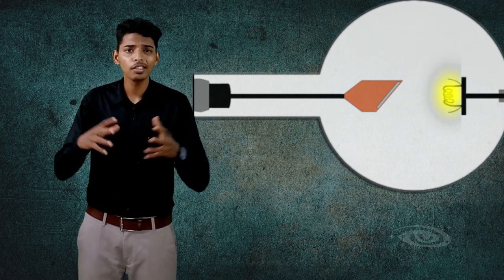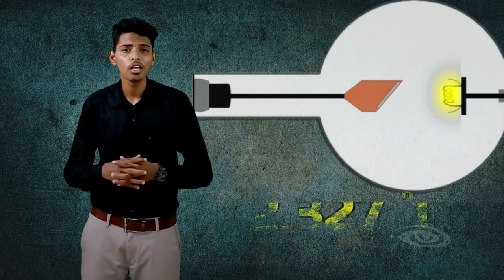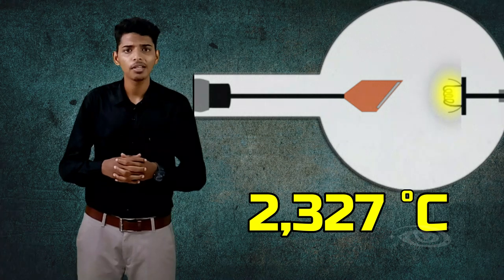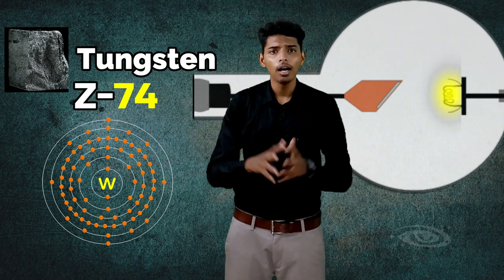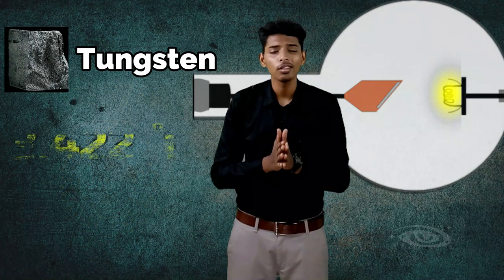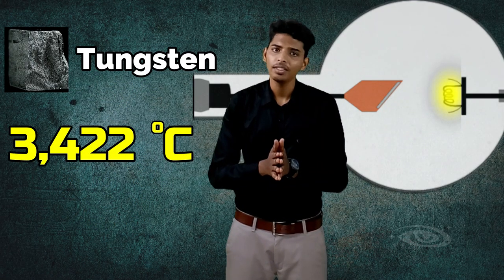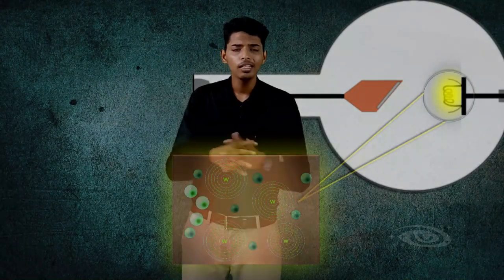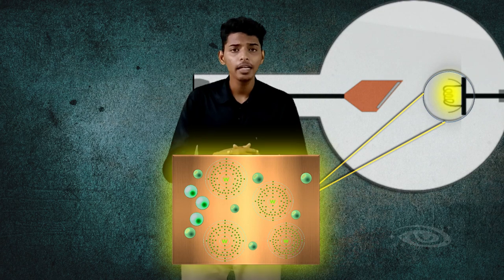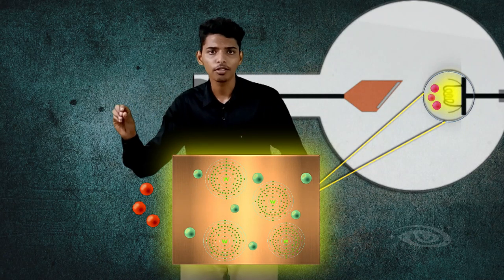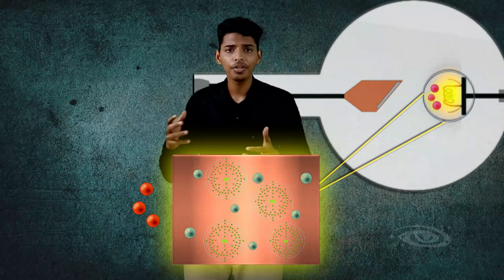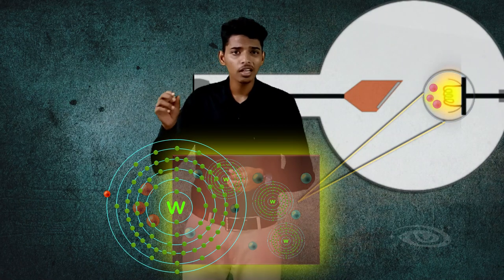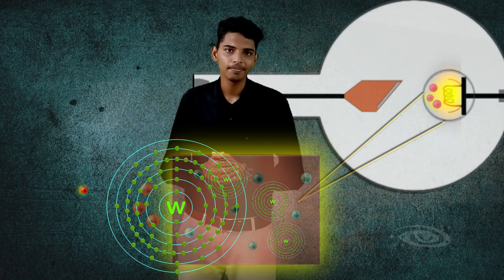When we give a tube current — that is, mA — to the cathode, the cathode filament gets heated to a high temperature. The thermionic emission temperature is 2327 degrees Celsius. To withstand this high temperature, we use tungsten because it has a high atomic number of 74 and a high melting point of 3422 degrees Celsius. The free electrons inside the metal gain kinetic energy and come out from the metal surface. Increasing the tube current causes more heat, causing outer electrons to come out as well.